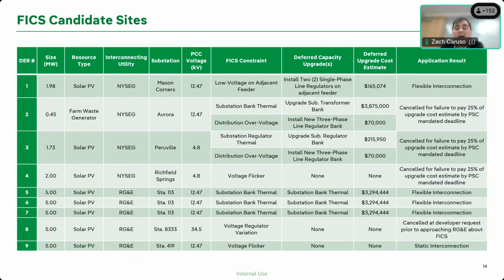And we can see the cost difference between the voltage constraints here and those substation thermal constraints. We can also see the general dropout rate of a number of these projects, right? Most of these projects that did not choose flexible also did not choose a static interconnection. So that would indicate that not only was flexible not viable for them, neither was the static approach. So when it comes to comparing the two, we feel that's a good demonstration that while we did talk to these sites, they didn't end up choosing flexible interconnection. Flexible interconnection is still a viable option if we can find the right site, as we did with the Spencerport sites.